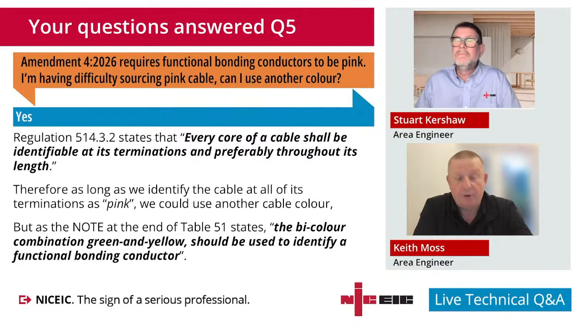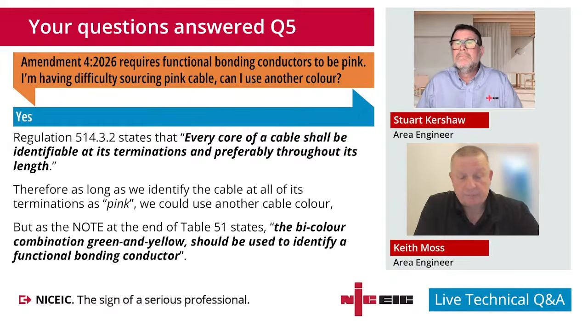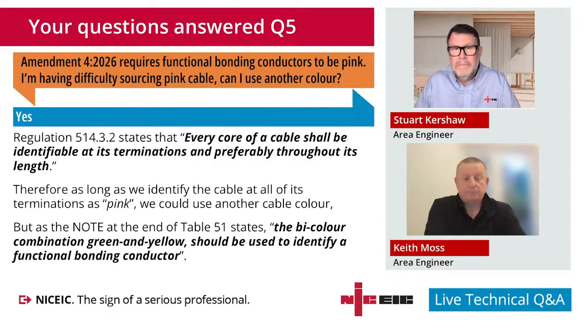But whatever colour you use, if for example you use the black one, you would then indicate it pink at both ends of the terminals, and somewhere else it was visible. If it was along the tray, you could then put some pink tape on it or a pink oversleeve. It's one of those instances where it has to be identified at each of its terminations, and the regulation says preferably throughout its length. So that's what enables us to use a different colour conductor, and then just label it.